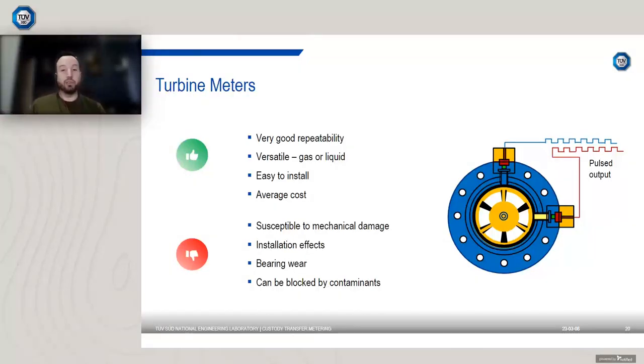So these are a well-established flow measurement technology, and they have a number of advantages. They tend to have very good repeatability. They're versatile in the sense you get designs for gas or liquid. Now, unlike an orifice plate, it's a different design for gas or liquid, so you can't use a gas turbine meter with liquid. It's usually one or the other, but the technology is suitable for gas or liquid. They're easy to install. Typically, it's just a flange piece of pipe, and they're relatively average cost, so they're going to be slightly more expensive than an orifice plate system, but they're not as expensive as some of the modern technologies that I'm going to talk about.